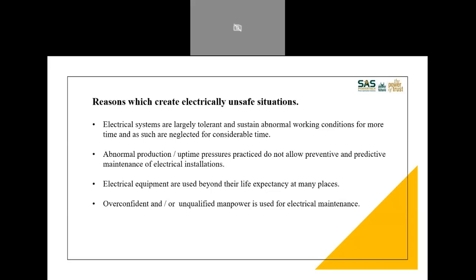Whereas when we come across American or Western companies working in India who work in the financial sector, which is equally or if not more sensitive, they also give a 48-hour shutdown every 6 months for testing electrical safety and electrical equipment, and they get them certified so that it works reliably later on as well. So these pressures also are one of the reasons electrically unsafe situations exist. Electrical equipment is used beyond its life expectancy at many places. We have seen establishments running 20, 30 years continuously; the technology has changed, many spares are not available, still the same equipment is carried. This is also another reason.